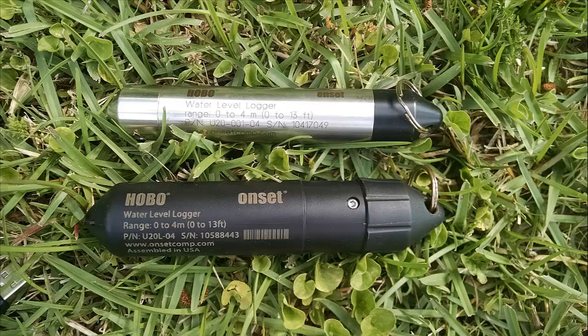The sensors we use come in two different styles, both seen here, one with a black plastic body and another with a stainless steel housing. Notice the range of the instrument is printed directly on the body itself, so 0 to 4 meters or 0 to 13 feet. So it's important not to deploy these sensors beyond that depth of 13 feet below a static water level.